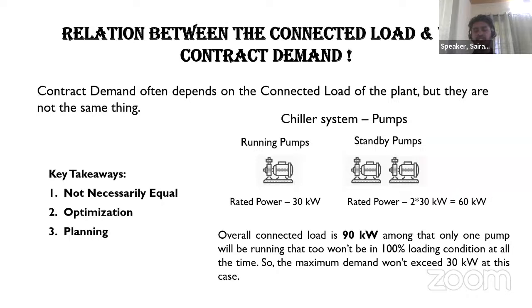The running pump is one, and the standby pump is two. Together, if we sum all the rated capacities of all these pumps, including the running pump and the standby pumps, we will get an overall connected load of 90 kilowatt. Among these, the standby pumps are meant only for operation once the running pump is under fault condition, or if any problem comes in the running pump. So here the connected load is 90 kilowatt, but we will be using only the 30 kilowatt.